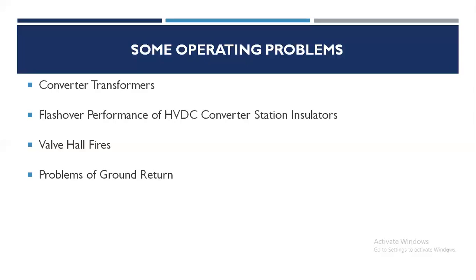As the magnitude increases, there is a distinct audible hum at fundamental frequency. The increase of the hum is noticeable when the DC current per phase exceeds the magnitude of the magnetizing current by the ratio of 1.2 to 1.5. At higher currents, the transformers may overheat due to increase in iron losses. The solutions to this problem are not simple. Blocking devices, that means capacitors in shunt with the protection arresters, are generally connected between the neutral and ground mat. Sometimes the neutrals can be grounded through resistors of a few ohms. Alternatively, capacitors may be connected in series with the three phases of the line to which the transformer is connected.